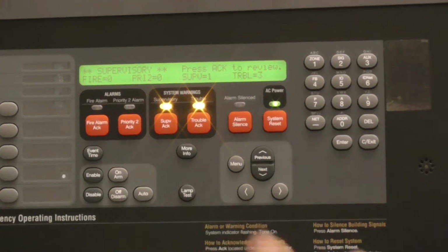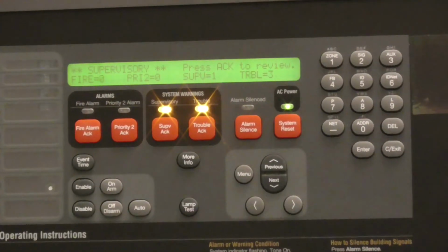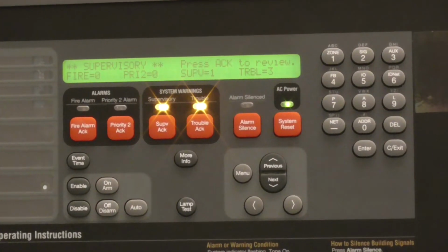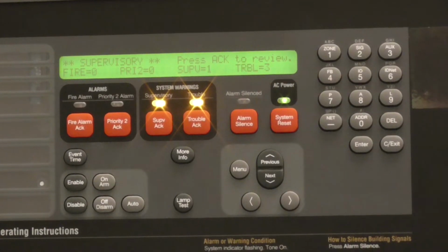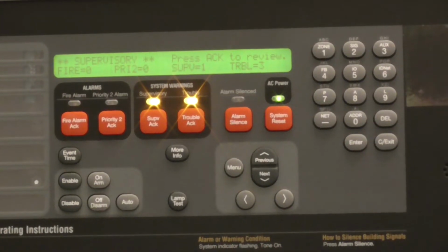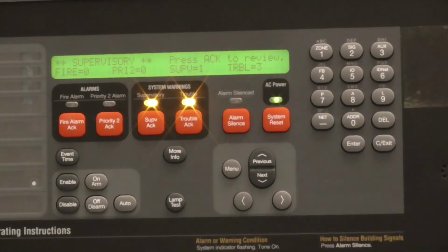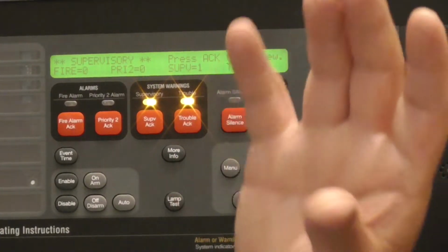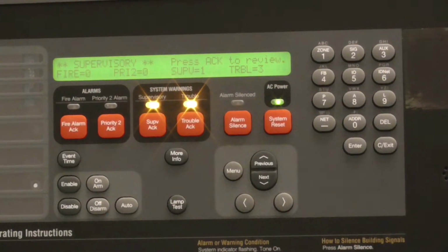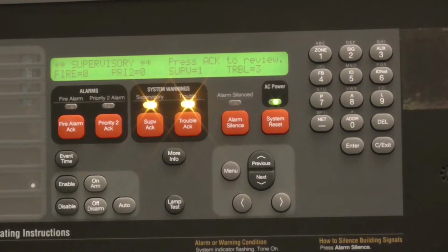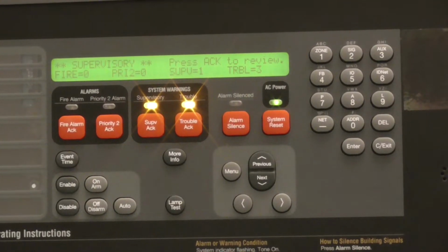So that's when it gets a little deeper. If they've already proven it's not an actual alarm or there's nothing wrong, and this device won't clear, they might have to come out, try to clear the device, take it off, blow it out, put the device back up, and then see if it goes normal. If it doesn't, you could disable it, but that's up to how the school wants to handle it.